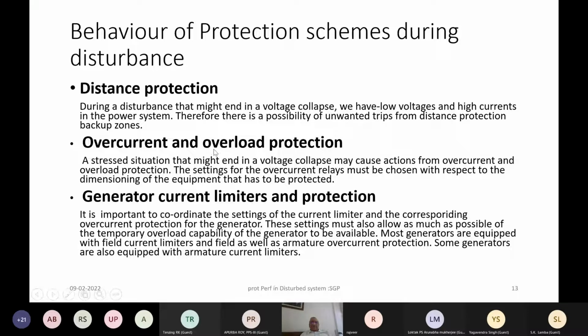There is a tendency by some of the utilities to mix up overload protection with overcurrent protection. One aspect which has to be remembered is that overcurrent protection on the transmission line is a backup protection to the distance relay for fault protection. So it's a protection against short circuit faults, phase to phase or phase to ground faults. Whereas the overload phenomenon is basically a three-phase phenomenon. It's not a fault condition. So the phase overload relay setting should not be such that short time overload results in phase overload relay operation.